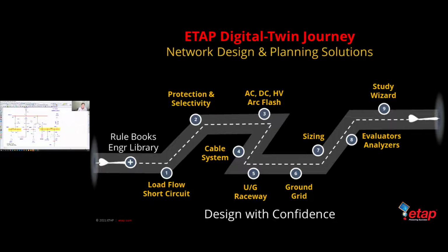Now I can run a single fault at a single location. This allows me to graphically animate the order in which your devices trip, so I can clearly see that my protection and coordination is done well for this location.